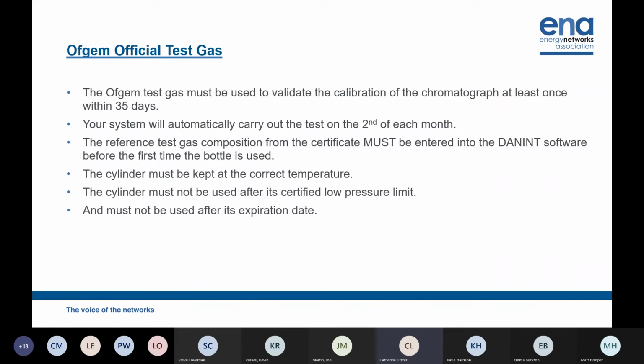And the same as the calibration gas, it must be kept at the correct temperature. You don't use it below the low pressure limit, and especially for the test gas, it must not be used after the expiration date. For the test gas, it's 5 years. Because it's not used very regularly, the chances are that this will go out of date before you run out of gas. So you must keep an eye on the date that it expires and change it prior to that, so that we don't cause loss of records. Anyone got any questions on that one? Nope. Next slide, please, Katie.